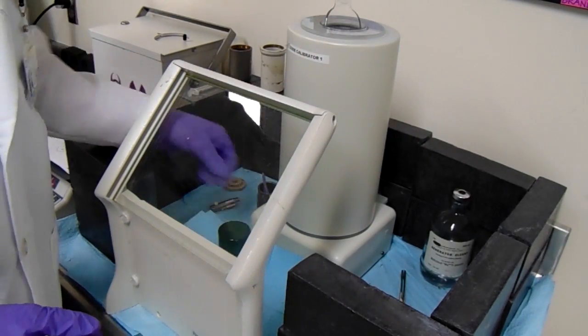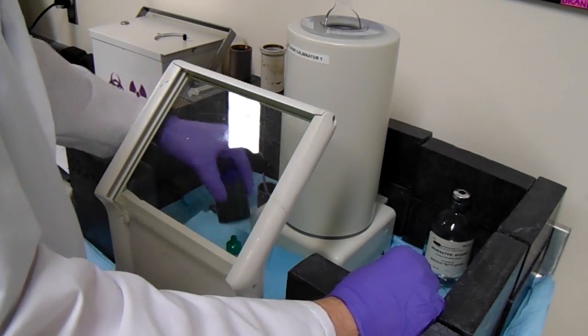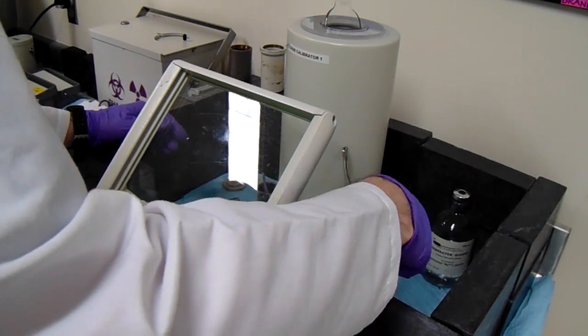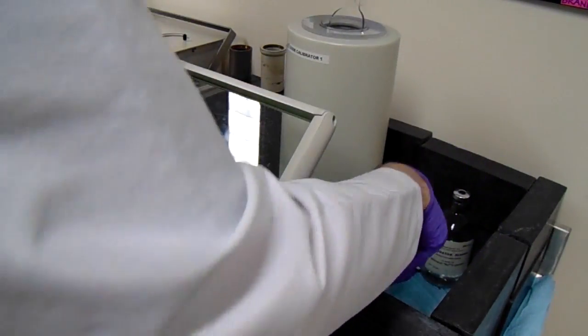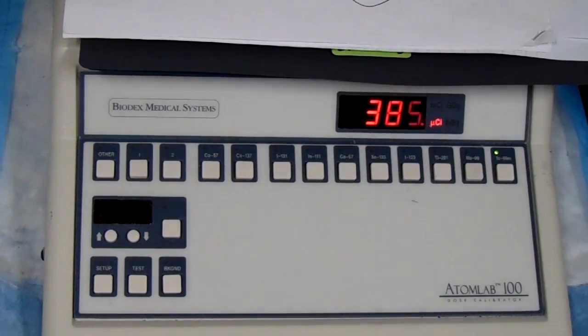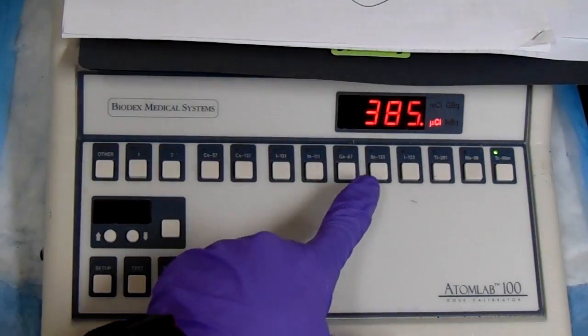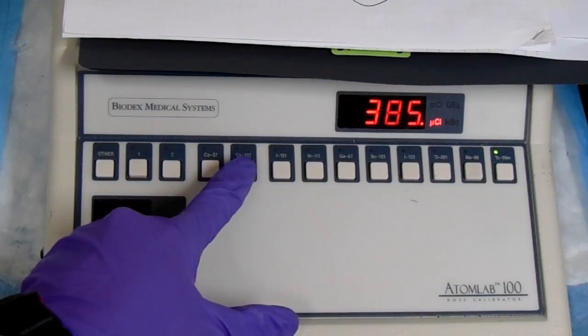Now what you're going to do is right here, you're going to do a background on the calibrator before you bring the source over. That's one of the things that I forgot to put in. And then you're going to take the source, put it in the plastic sleeve, and go over to your panel and take it from technetium and go to cesium.